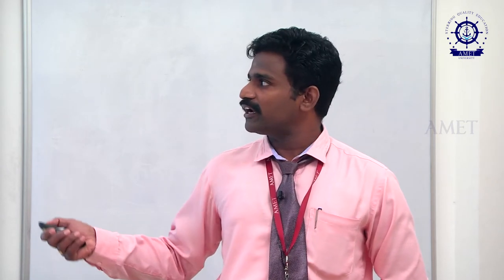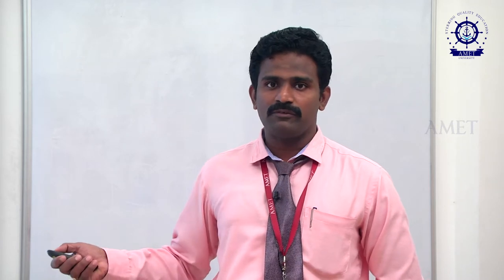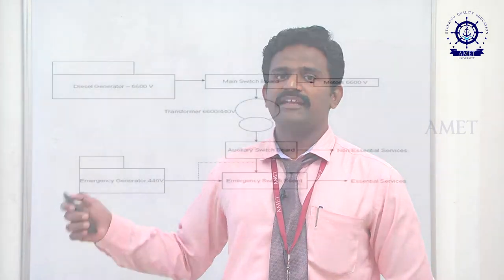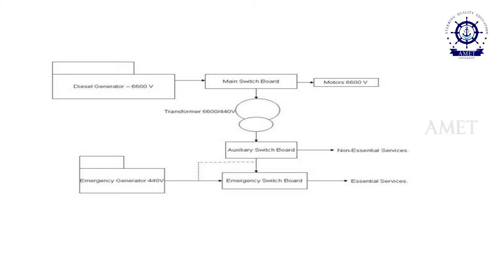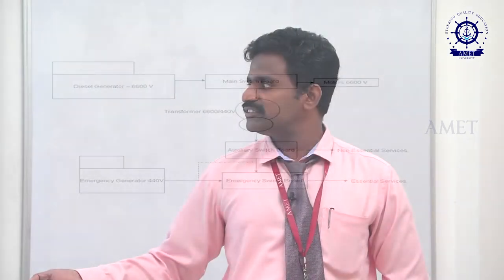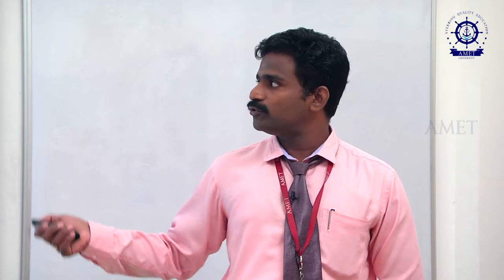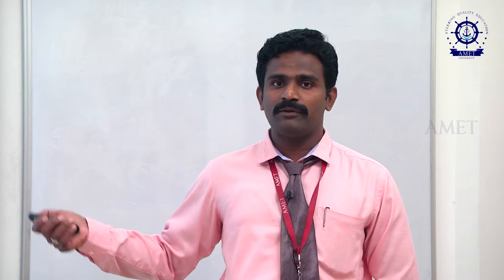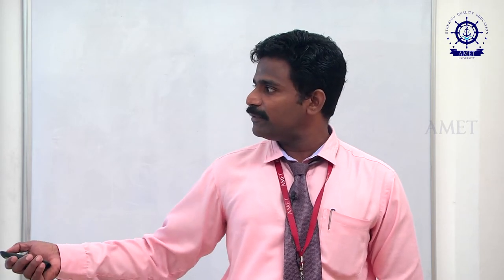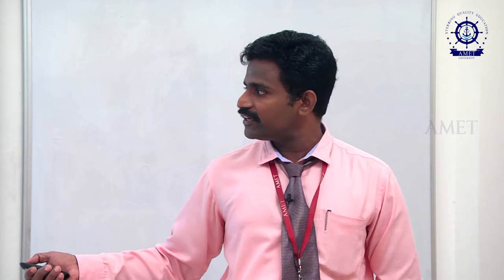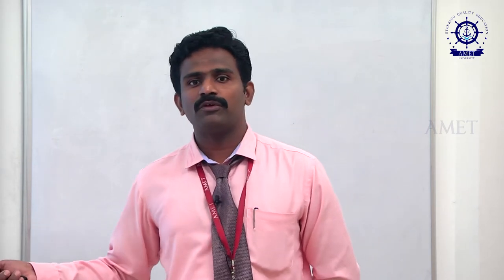When the power to the main switchboard is cut off, automatically within the next 3 to 45 seconds, the emergency generator will turn on and supply power to the emergency switchboard. When the supply is cut off, the emergency generator turns on, and the interlock between the two switchboards opens. Then the interlock between the emergency generator and the emergency switchboard closes. This is the main working operation.